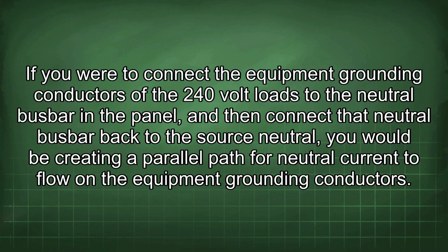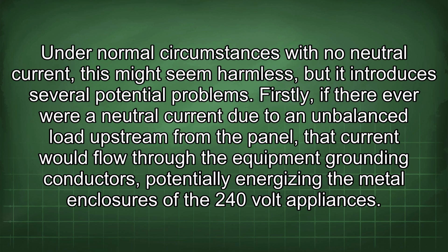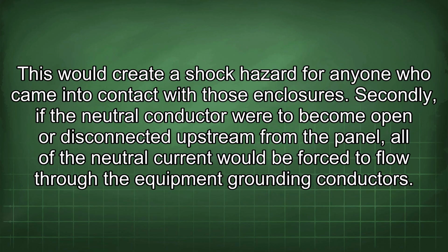If you were to connect the equipment grounding conductors of the 240-volt loads to the neutral busbar in the panel, and then connect the neutral busbar back to the source neutral, you would be creating a parallel path for neutral current to flow on the equipment grounding conductors. Under normal circumstances with no neutral current, this might seem harmless, but it introduces several potential problems. Firstly, if there ever were a neutral current due to an unbalanced load upstream from the panel, that current would flow through the equipment grounding conductors, potentially energizing the metal enclosures of the 240-volt appliances. This would create a shock hazard for anyone who came into contact with those enclosures.